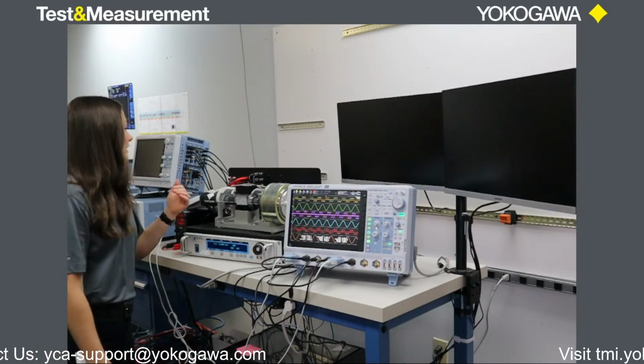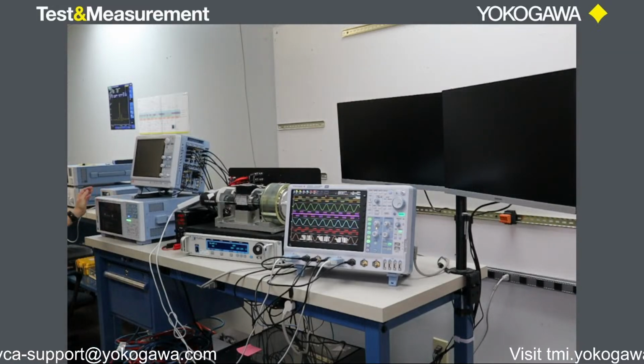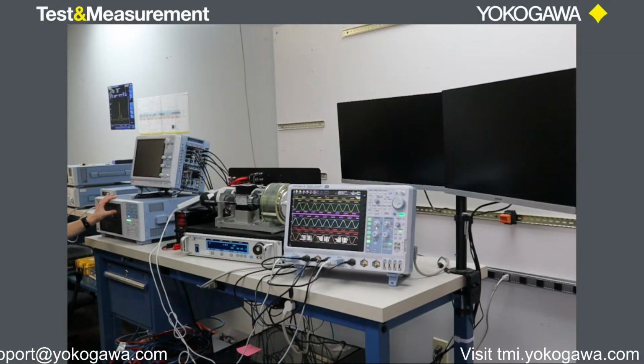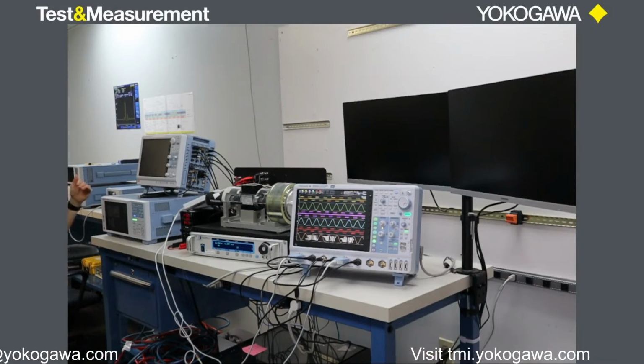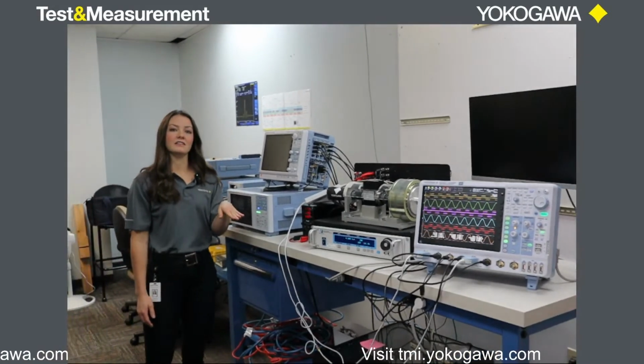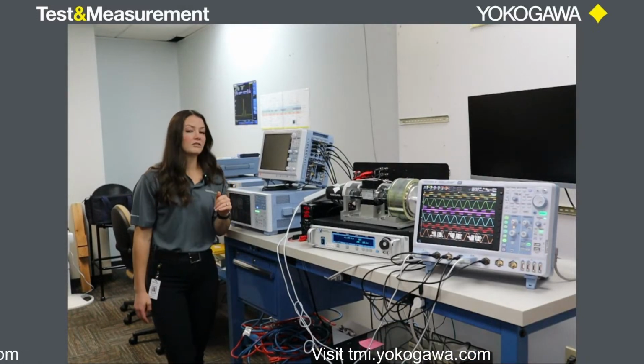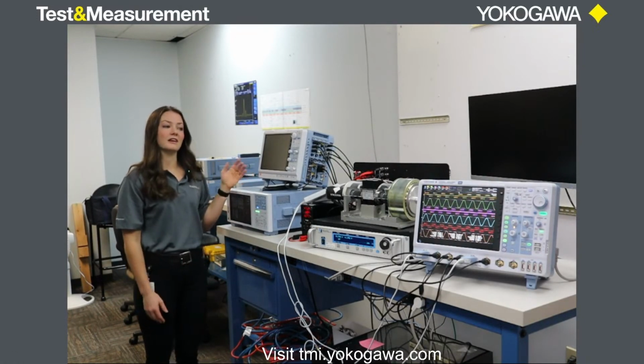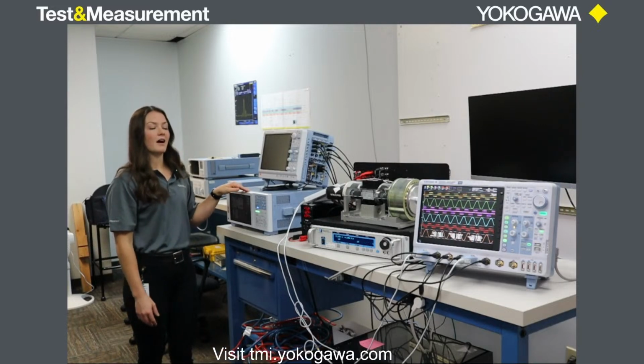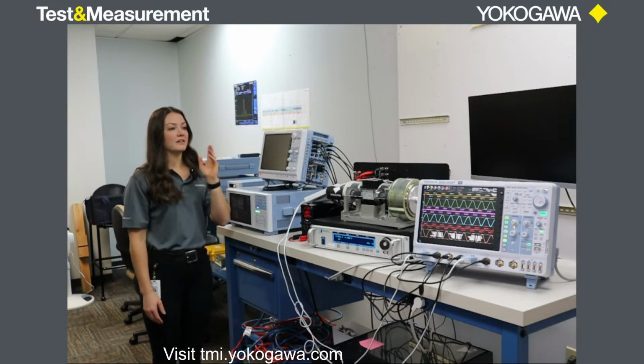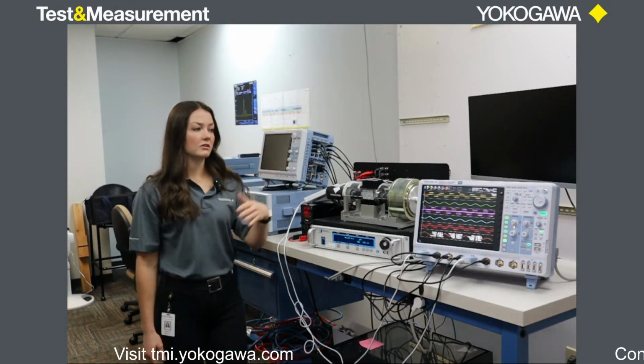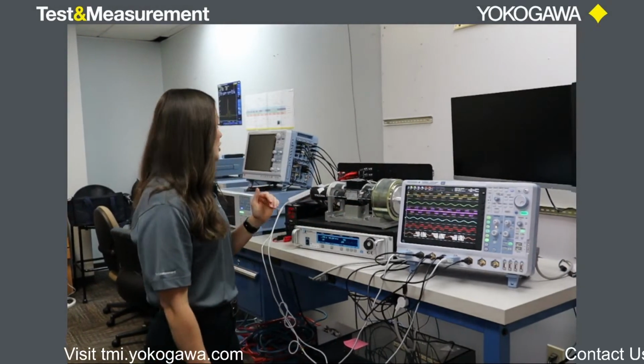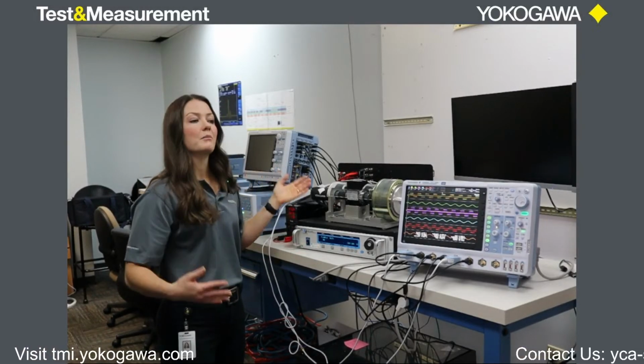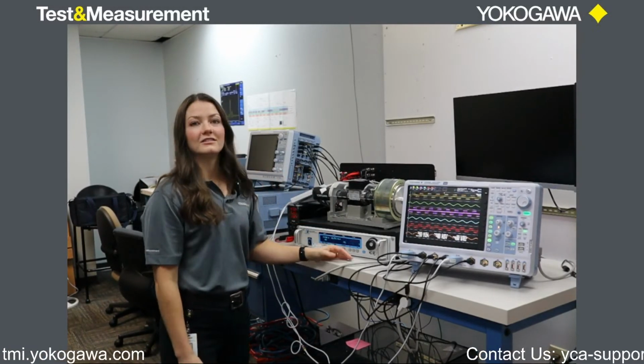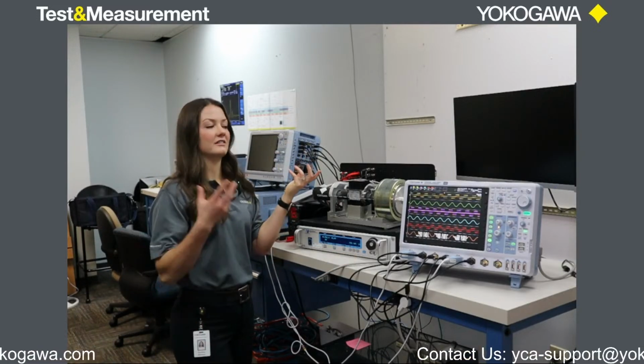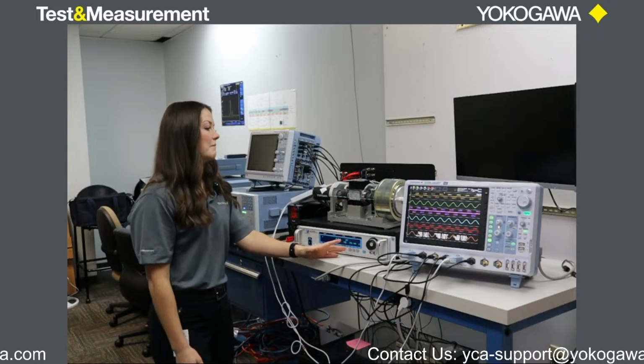One other really cool thing, I don't know if you can see it, but we have a power analyzer over here that you can actually synchronize with the oscilloscope through IEEE 1588. What the power analyzer is really good at is getting super accurate voltage, current and power data. What the oscilloscope is really good at is getting this really fast waveform data. So you can time synchronize these, bring them into our software, and see all the data that you need and get that accuracy and the raw waveform data at the same time.